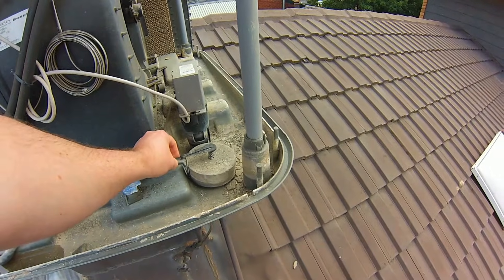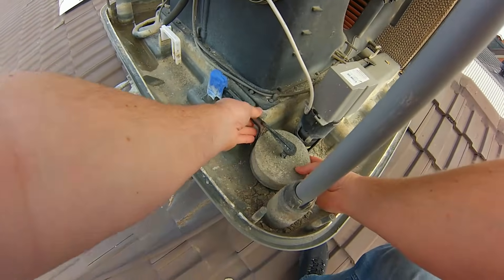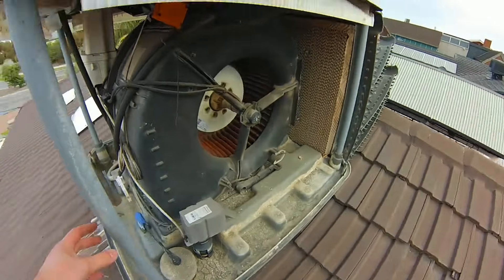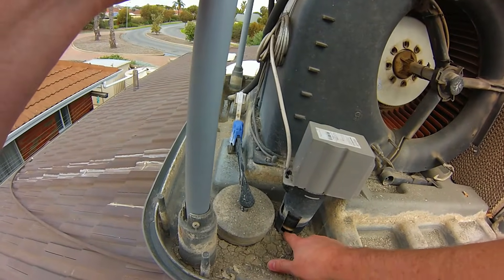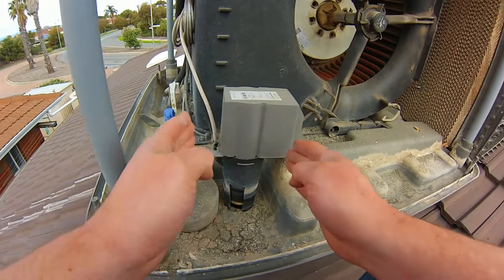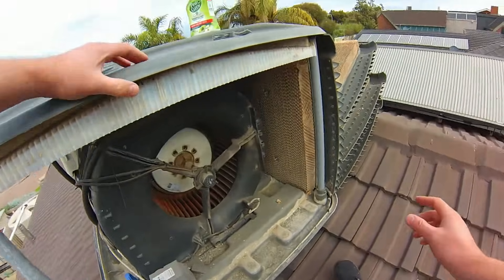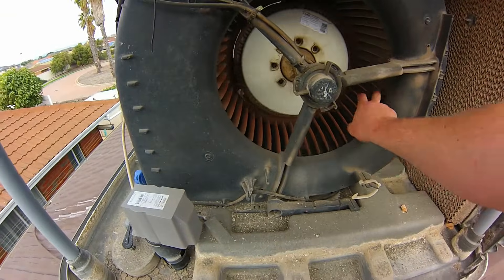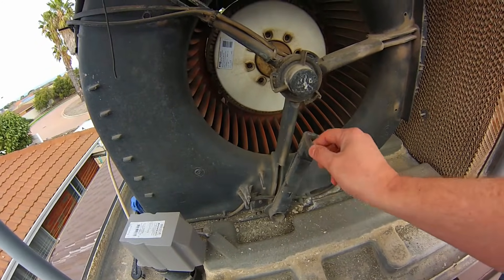The water level float valve is a simple device that keeps the water level constant due to evaporation — you can adjust the level by adjusting the float up and down. The Breezair dump valve is a 24-volt AC unit; it closes to hold water and opens to dump it. As an electrician I've replaced so many of them — they're absolutely junk. This is the direct drive drum motor, a dual fan drum drive which is very efficient.